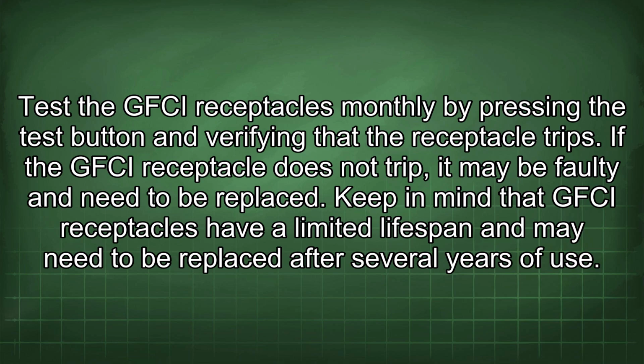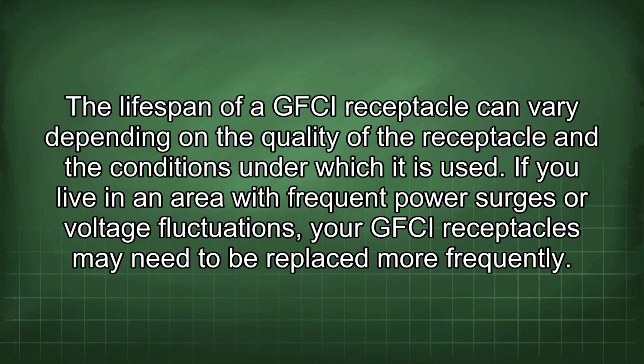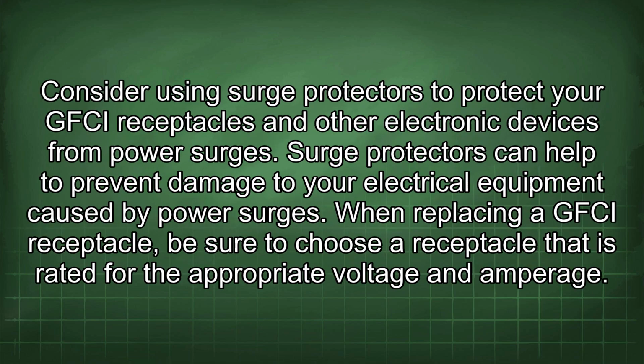Keep in mind that GFCI receptacles have a limited lifespan and may need to be replaced after several years of use. The lifespan of a GFCI receptacle can vary depending on the quality of the receptacle and the conditions under which it is used. If you live in an area with frequent power surges or voltage fluctuations, your GFCI receptacles may need to be replaced more frequently. Consider using surge protectors to protect your GFCI receptacles and other electronic devices from power surges. Surge protectors can help to prevent damage to your electrical equipment caused by power surges.